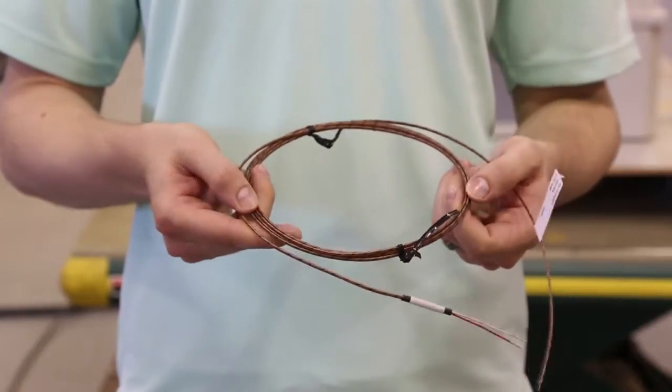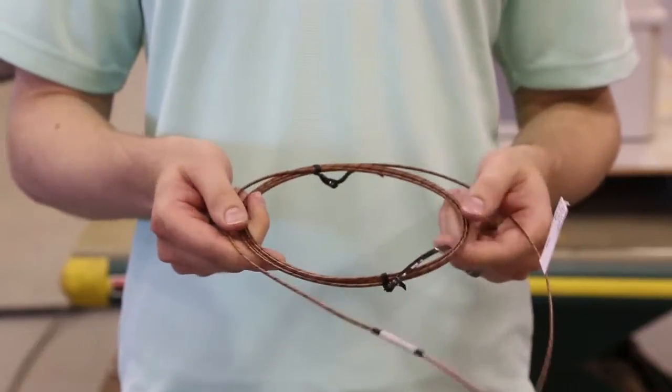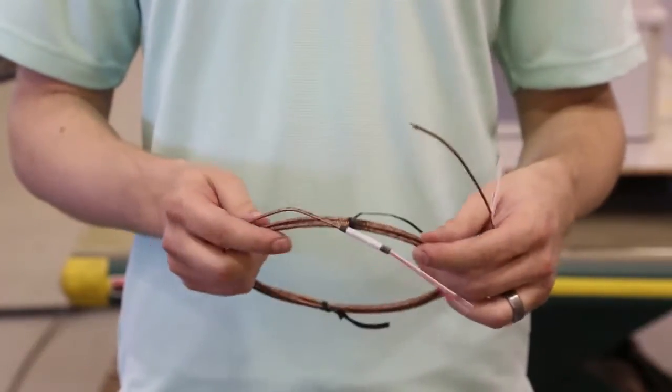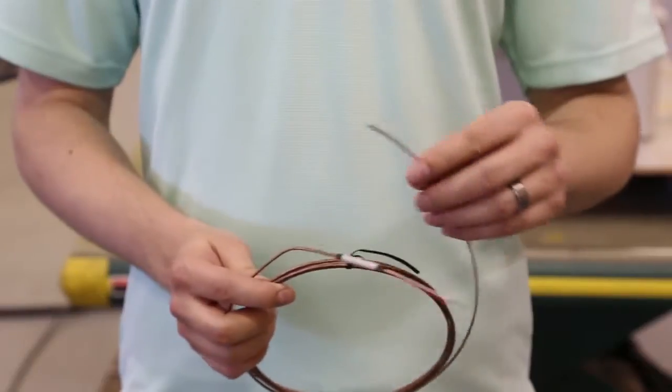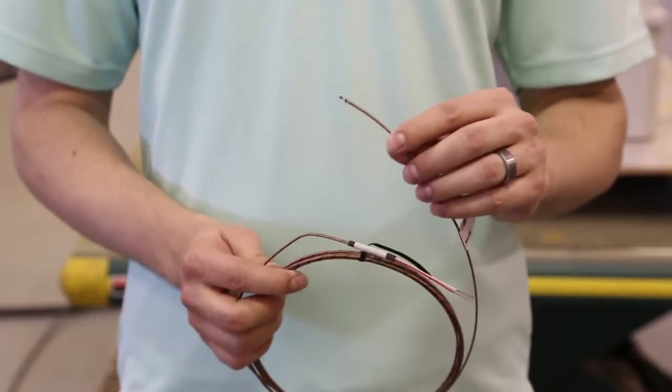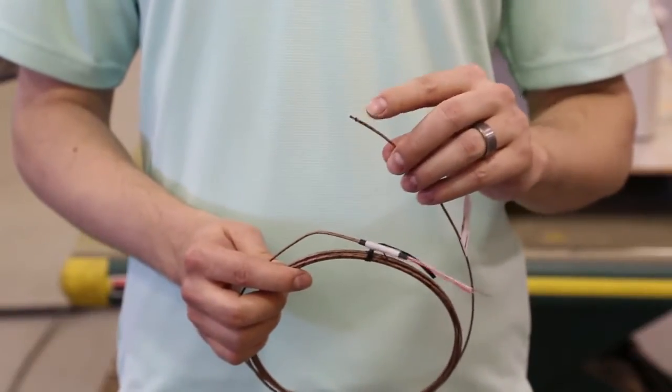Make sure that the insulation is not frayed or damaged to avoid bare wires making contact with metal on the oven. The tip of the thermocouple should be welded, not twisted, together.